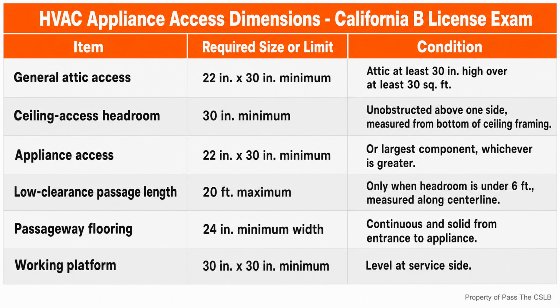Suppose the mechanical crew lays an insulated duct directly across the catwalk because it is the shortest run. The duct may fit and the air system may even perform, but the service passage no longer functions as intended. The practical correction is to coordinate an approved reroute or another compliant solution without damaging the structure or the duct. I would never treat climbing over fragile ductwork as the plan.